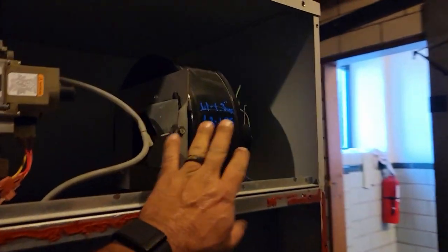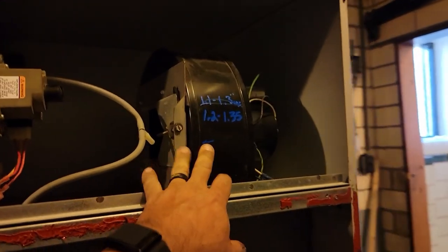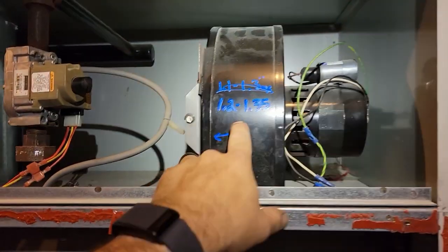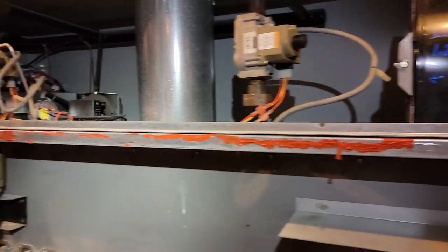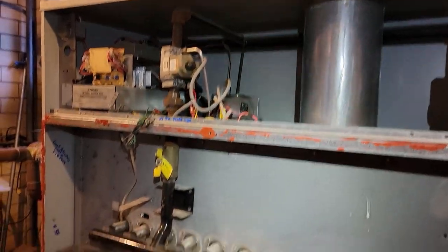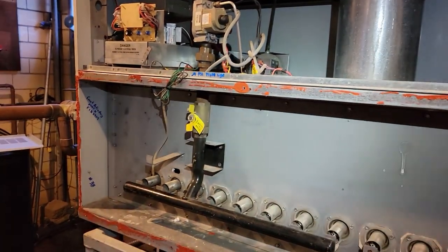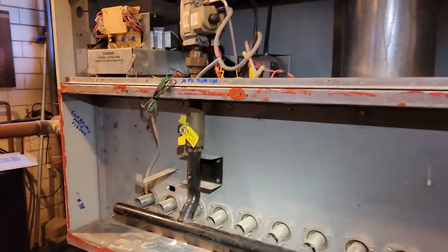I ended up adjusting my air here a little bit. The book I had was off, was not accurate, so I called the factory today. Got it set for what they said it was supposed to be. Also checked gas pressure because the burners were sitting there lifting, the flames were lifting up off the burner.